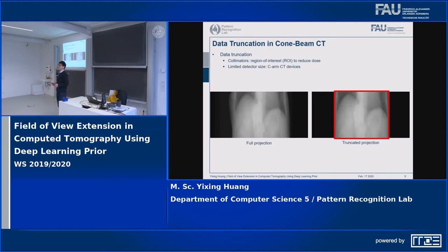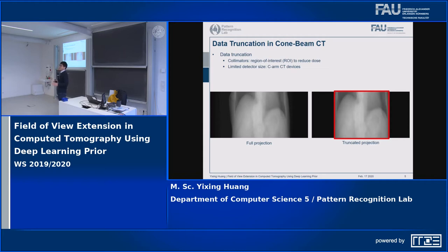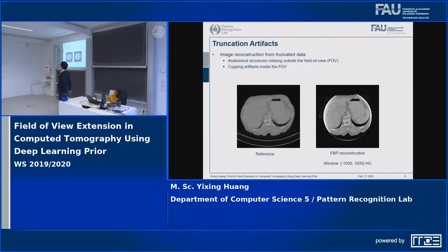The other scenario is due to the limited size of flat panel detectors — they are not large enough to cover the whole body. Human heads are not so big, so it is fine to cover the whole head. However, for the abdomen and torso, because they have a much bigger size, the detectors are not large enough. In practice, we only get projections within the ROI detector region, so the projections are laterally truncated.